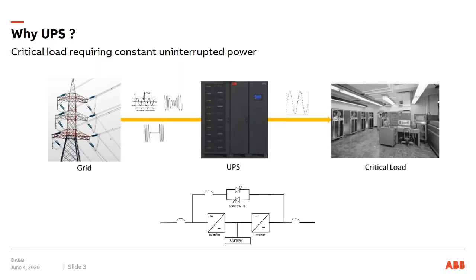And UPS manufacturers figured out a couple of decades ago that if you fire the static switch and use that as the normal mode, then power is coming directly from the utility going to the load, and now we only have the losses in the static switch, which is roughly 1%. So now the efficiency is suddenly 99% for this system. So it's been around for a long time. Hardly anybody uses it because that's not why they bought a UPS in the first place. Because now the power is being fed directly from the utility.